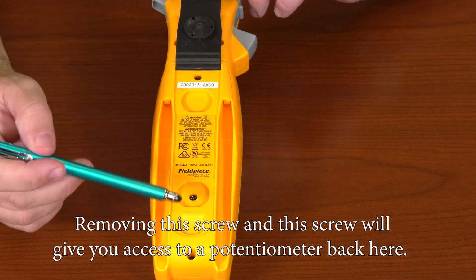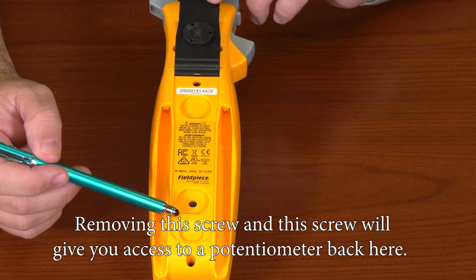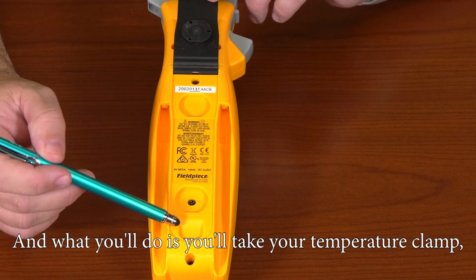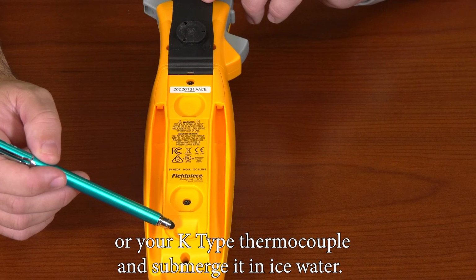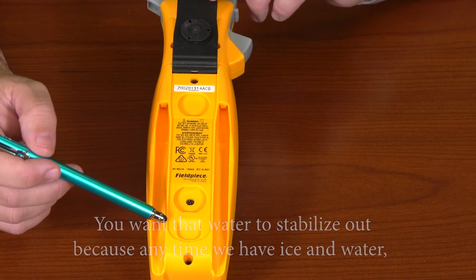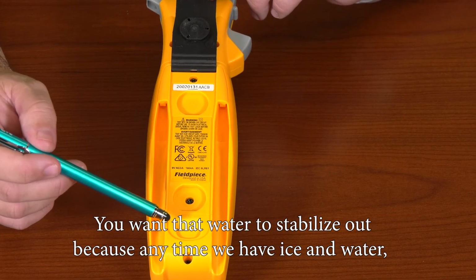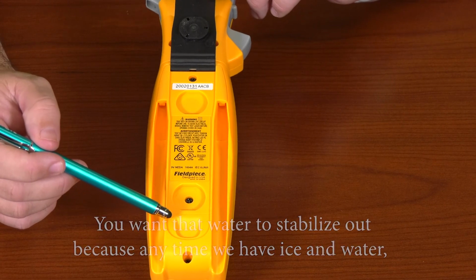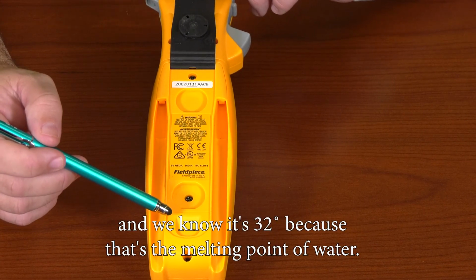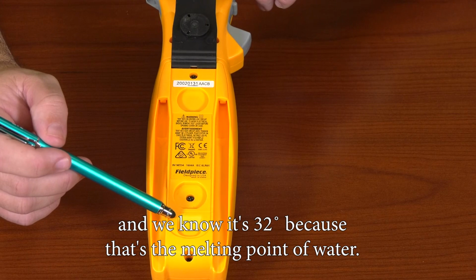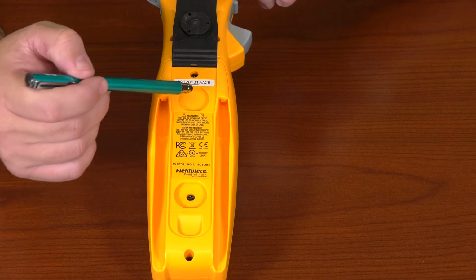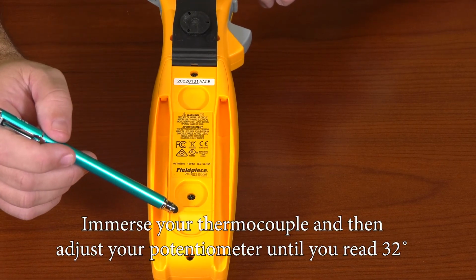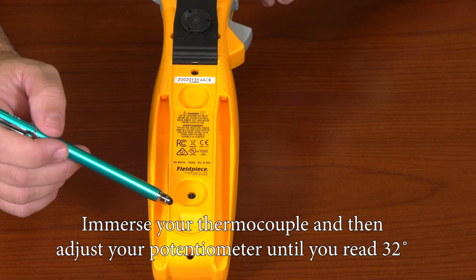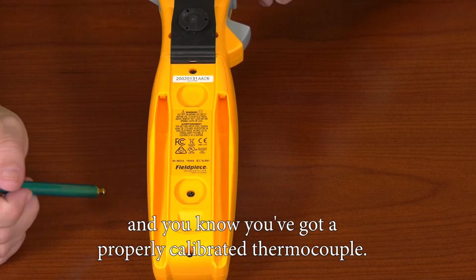Removing this screw and this screw will give you access to a potentiometer back here, and what you'll do is take your temperature clamp or your K-type thermocouple, submerge it in ice water. You want that water to stabilize out, because anytime we have ice and water, it's a saturated mixture, and we know it's 32 degrees because that's the melting point of water. Immerse your thermocouple and then adjust your potentiometer until you read 32 degrees and you know you've got a properly calibrated thermocouple.